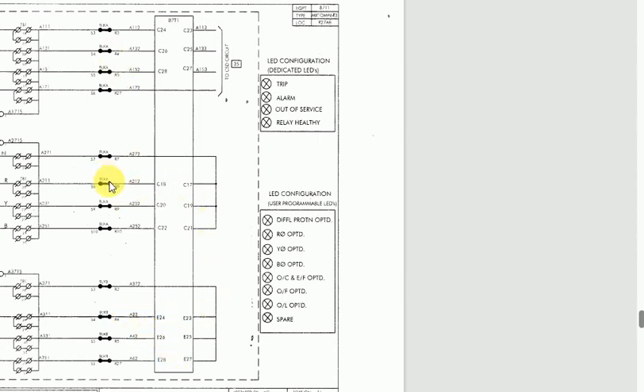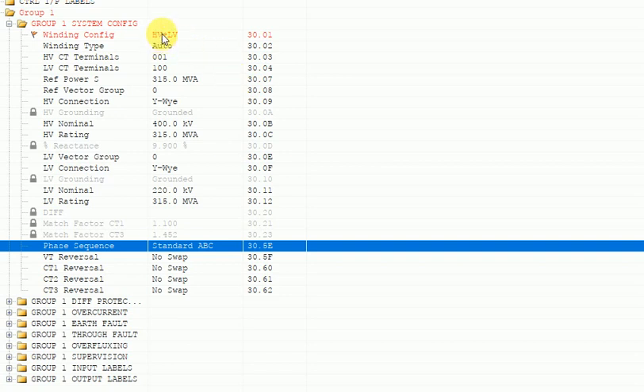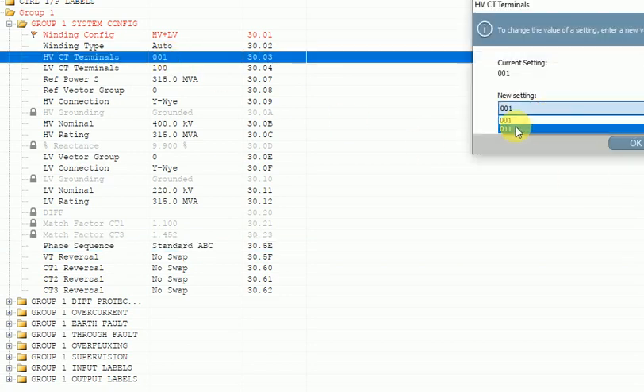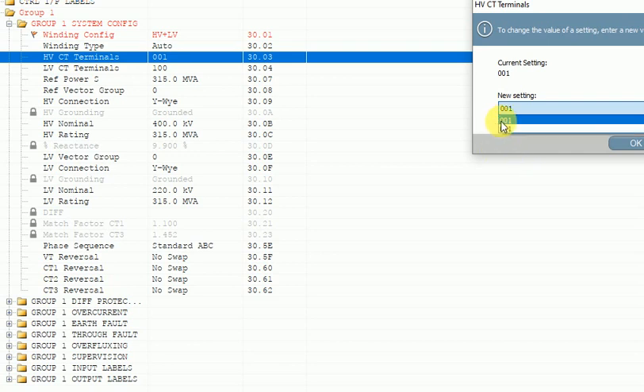Here I have two HV CT terminals, so how to configure the CT input in system configuration? In this case, I still select HV plus LV because HV terminal has two CTs and LV CT has only one. But for the HV CT terminal, since I have two HV CTs, I have to select 011 — meaning in the HV terminal there are two CT inputs wired from the HV side. 001 means one CT as HV input; 011 means two CTs as HV input.